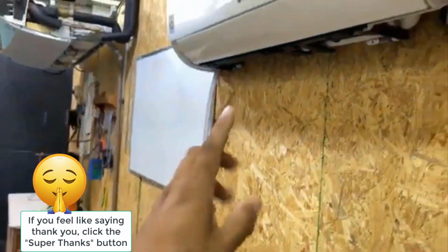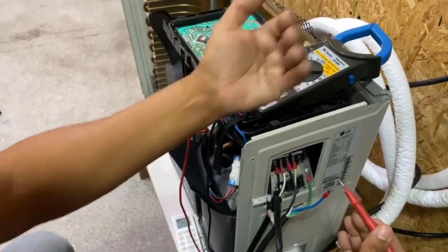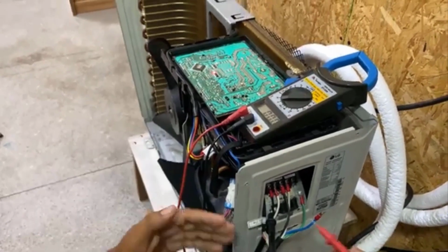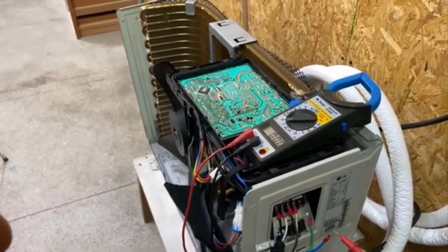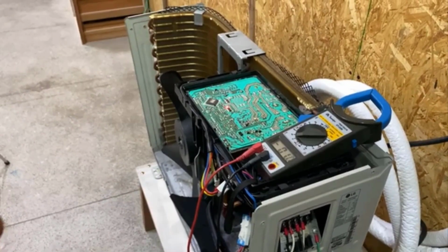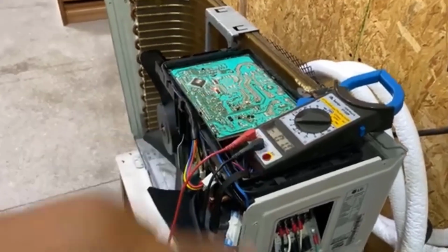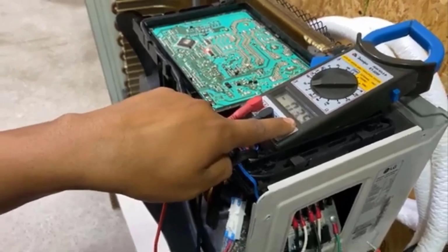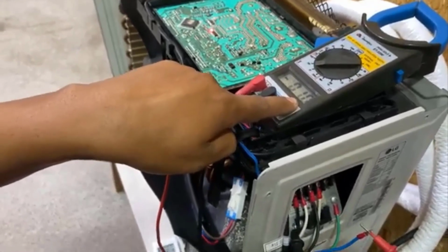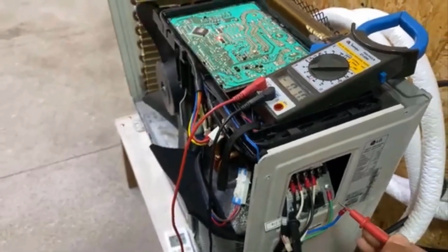Causes of communication problems. Electrical problems. Damaged interconnection cable: cables with loose connections, broken wires, or compromised insulation can interrupt the flow of data. Polarity error: if the cables are connected incorrectly, positive to negative for example, communication will be impaired. Lack of grounding: the lack of proper grounding can generate electrical noise that interferes with communication signals.